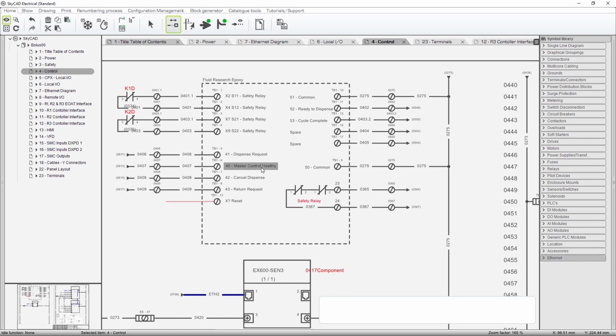This is a heartbeat signal, and there's a variety of ways that you can program that. And if that's not high, then the epoxy dispense is going to ignore a dispense or a cancel. So that's like a heartbeat from another system, a main system, to this. Okay, that's the epoxy dispense. And I showed it as a dashed line because it's not in this panel.